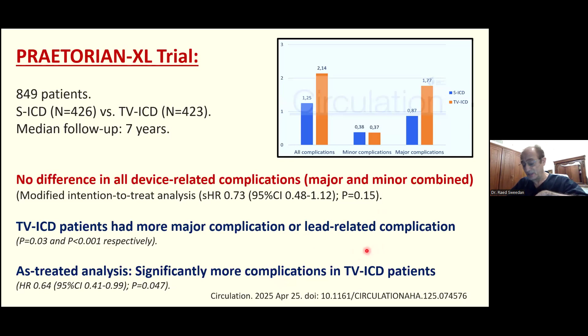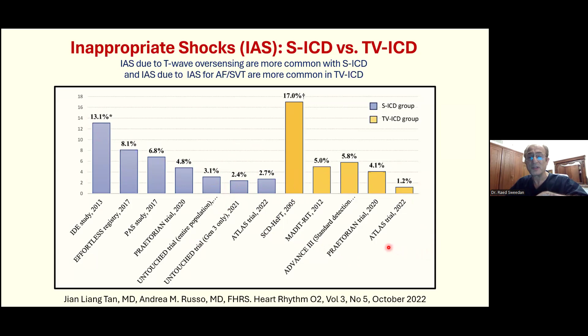subcutaneous ICD. If you look at the inappropriate shocks, as with every technology, you start with really high inappropriate shocks and it goes down as we improve our programming, and also in the case of the SICD, improve the software to decrease the T-wave oversensing. So as we go into the most recent trials, you can see that the inappropriate shock rate is around 4% for both SICD and transvenous ICD. So the inappropriate shocks have come down for the SICD to similar rates close to the transvenous system.